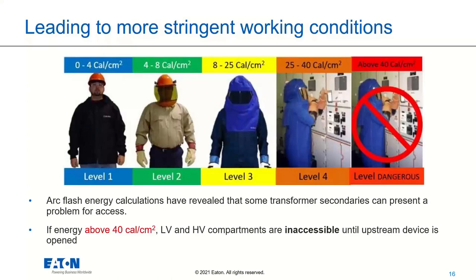And as we see, the change in complexity of 1584, the addition of all these different variables, we went from about, I believe, three or six variables on the 2002 to well over 18 and plus iterations on the 2018 version. So you can imagine it's much harder now to take into account all of these variables and determine if I'm calculating my arc flash in the right way. And that's where EasyPower can come in and help you guys out. It is really using a powerful tool rather than the back of the napkin calculation on what this can do for me.